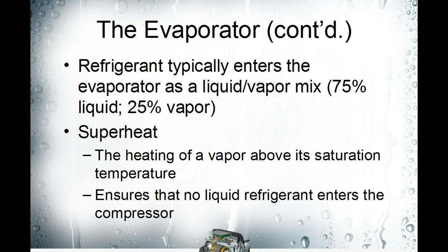When the refrigerant enters the evaporator, it does so through the metering device, and we're going to start right at that point. Because this is a cycle, there is no real good place to start, so we're going to end right back up at the metering device. When it enters the evaporator from the metering device, it flashes pretty quickly to a 75-25 mix. This is saturated refrigerant, which means if we add heat — which we're doing in the evaporator — it's going to cause it to change state.